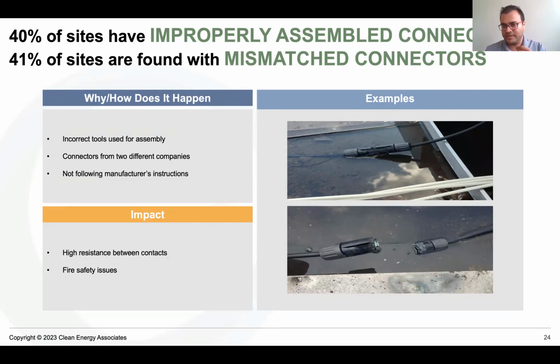So what CEA does is compare connectors installed at the same time and point out inconsistencies on the backnuts. We ask technicians on site to describe the procedure and do a visual inspection of the connectors, determining whether they used the right tools and the right procedure. There should be at least a couple of threads showing on the connectors, not completely loose, and that's one indication. Different manufacturers may have different specifications, so please check the manuals.